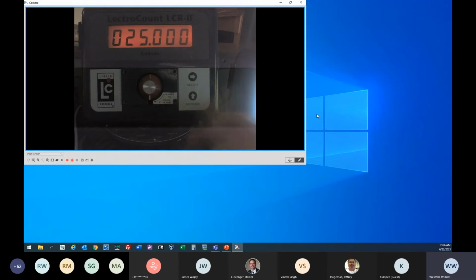Again, if you want to make another run, let's say you're off a little bit, just hit the select key or the increase key. We do a counter test, and we fill up our prover. Once our prover is full, we hit that increase key one more time. Then we change our number here to match exactly what's in our prover, and then hit select at that last one, and that'll lock in our prover quantity. So that's a little bit about the LCR2 with the lap pad and without the lap pad for calibration.